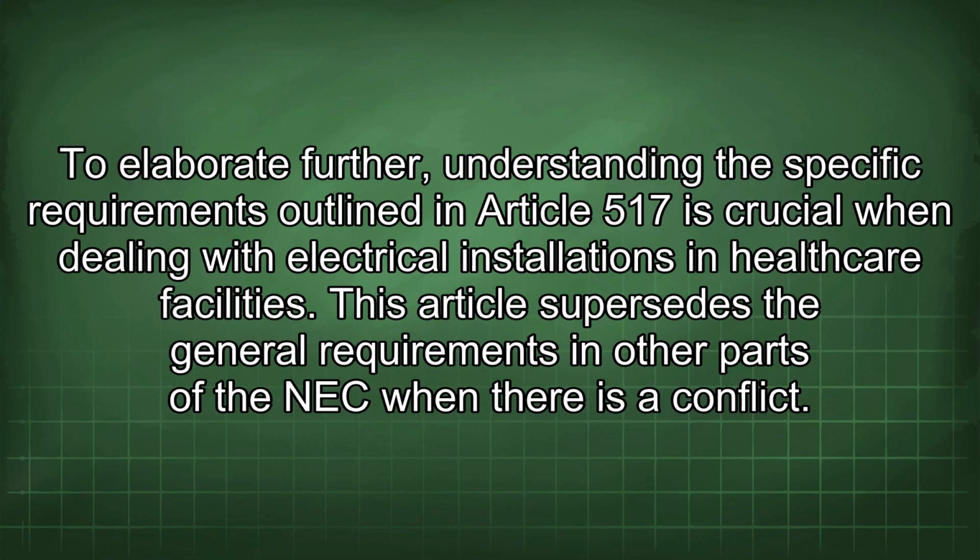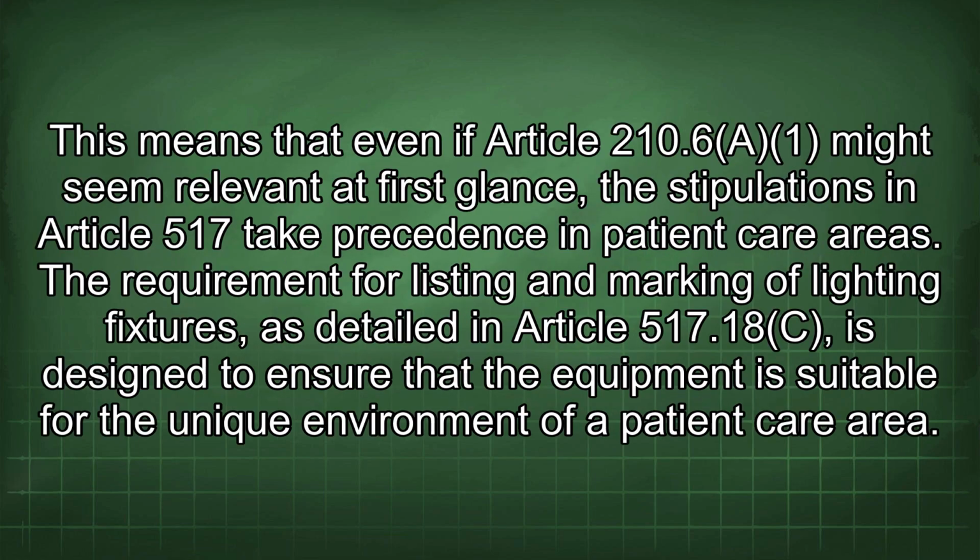To elaborate further, understanding the specific requirements outlined in Article 517 is crucial when dealing with electrical installations in healthcare facilities. This article supersedes the general requirements in other parts of the NEC when there is a conflict.